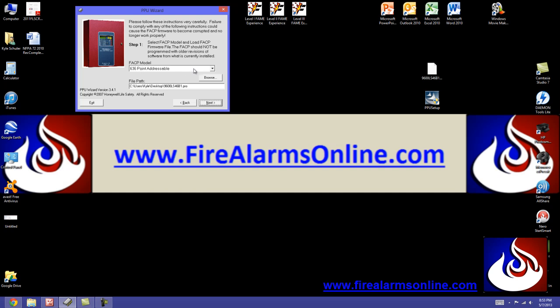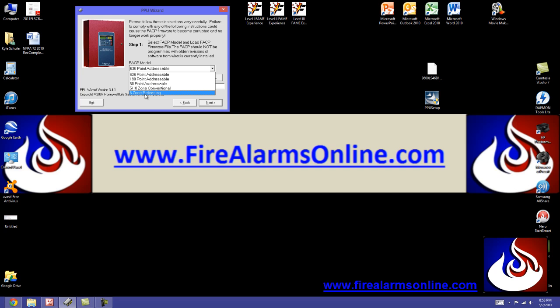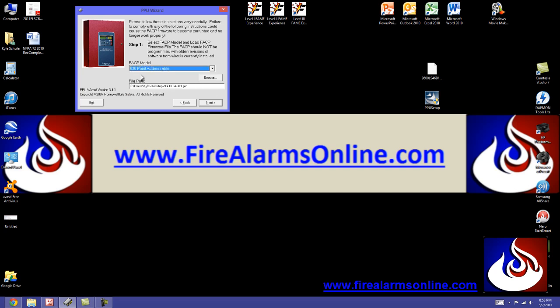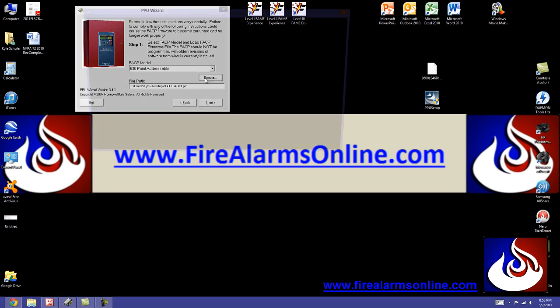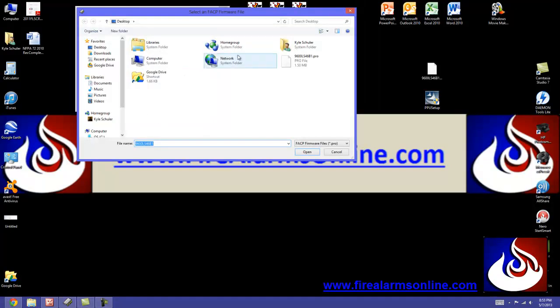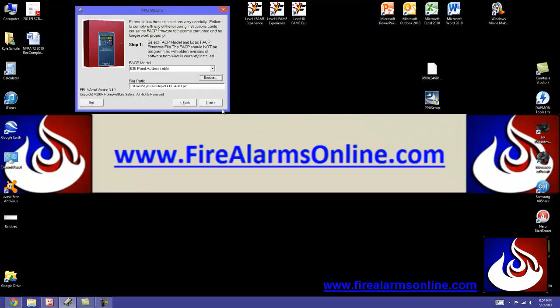Here is where we're going to select the panel that we're working with. And like I stated, we're going to be using the 9600 UDLS for the example. So we'll select 636 point addressable. And the file path is where you actually have the firmware file saved as. You're going to obviously have to extract that out of the zip folder when you download it. And it's going to be a PRO file. I have it on my desktop. So when you hit browse, just like anything else, just go ahead and find it right here on your computer. Open it up and it should show the path right here.